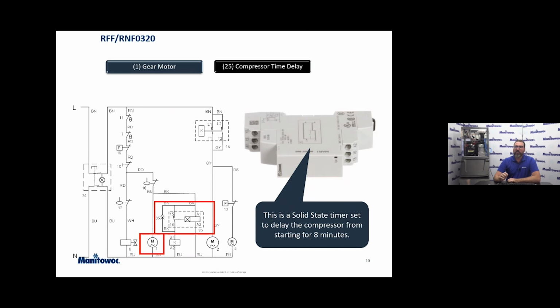We're going to plug that in, and that's going to bypass that time delay, and hopefully that compressor is going to start up, indicating that, okay, the compressor is functioning the way we need it to. Or maybe if it still doesn't start up, perhaps we have a problem with that compressor, or maybe there's a problem with this solid state timer to begin with. But that bypass is meant just for troubleshooting. Please don't leave that in. That's a safety. We need that time delay to be part of the function of that machine.